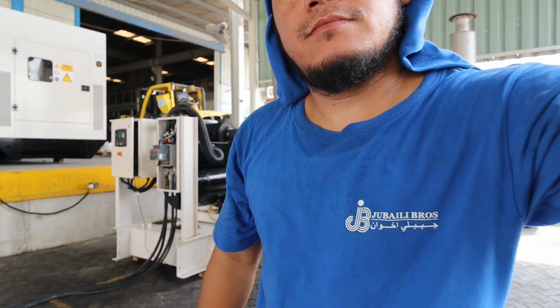So we're going to adjust everything and calibrate it properly so we can achieve proper synchronizing. Once it is stable and everything is working fine, we are going to close the breaker and put the load at 100%. After that, if it's okay and there's no negative circulating current, we will transfer to the other generator and start the load test as well. So let's go and start at this point.